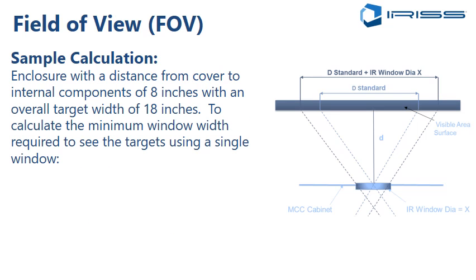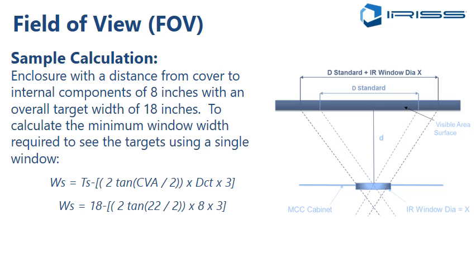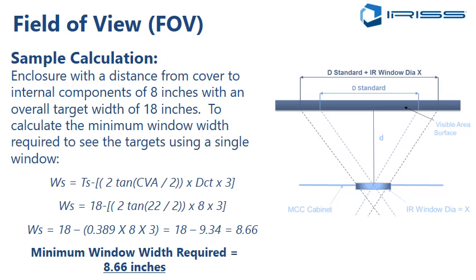In the sample calculation, we can look at an enclosure with a distance from the cover to internal components of 8 inches, with an internal target width of 18 inches. So that's my target size I'm looking at. To calculate the minimum window width required to see all the targets with one single window, we use the formula we listed in the slide before. The calculation is 18 minus 0.389, which is half the tangent of 22 degrees, times 8, which is the distance from cover to target, times the multiplier. So that equals 18 minus 9.34, which gives me a minimum window width required of 8.66 inches.